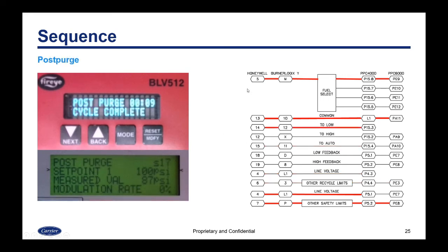And then when you're complete and you go to post-purge, the recycle limit is now open. The signal is going to go back to low. Depending on how quick it happens, you may or may not register post-purge on the PPC, but it's going to drive the servos to the low position. It's going to shut down, then it's going to drive it to the standby position after that's complete.